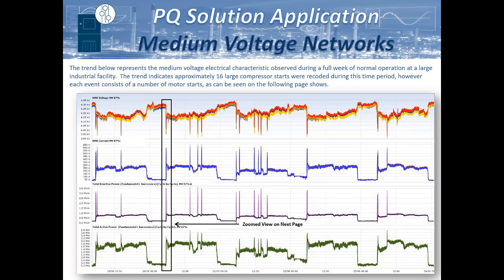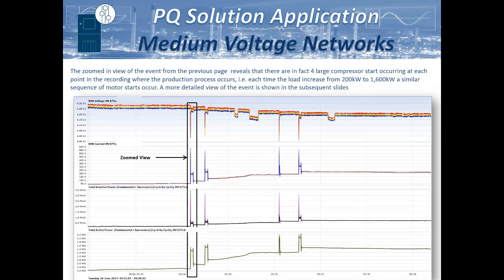You can see here, this is a large food processing facility throughout the US. On their 4160 side, they have 16 large ammonia compressors. When you zoom in to an area like this, you see that each one of these was 4 independent starts and had a fairly significant impact on voltage, dropping it down to below 4,000 volts.